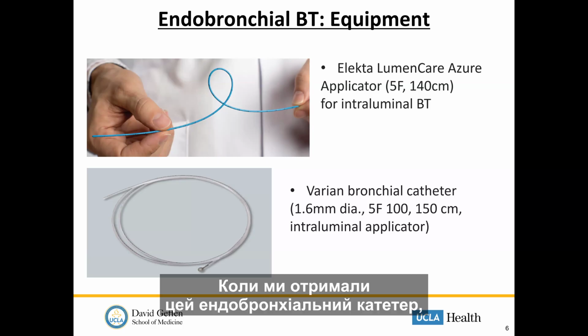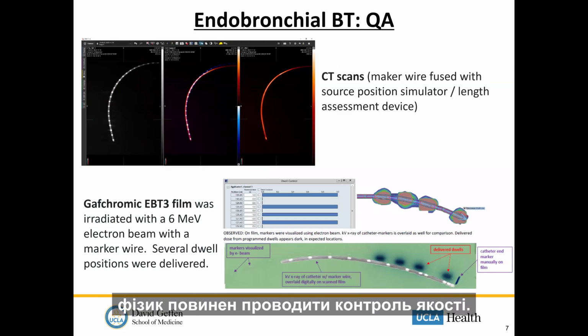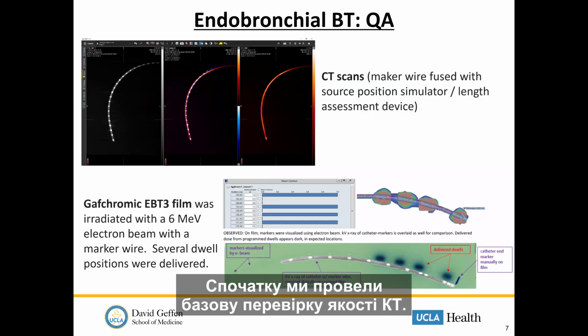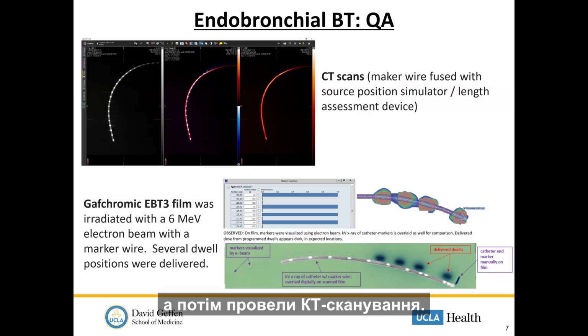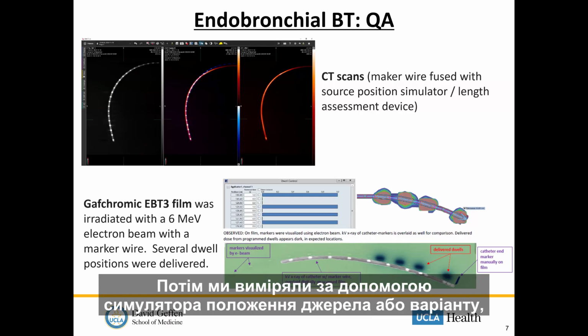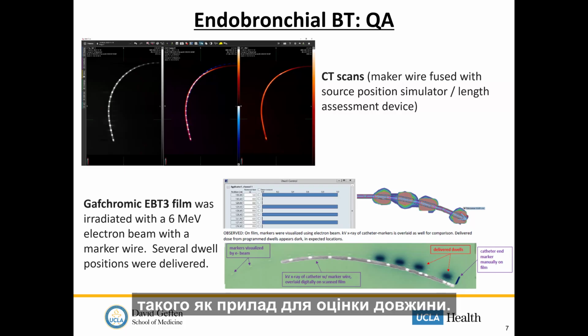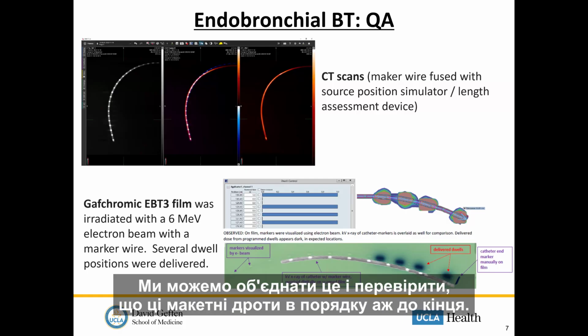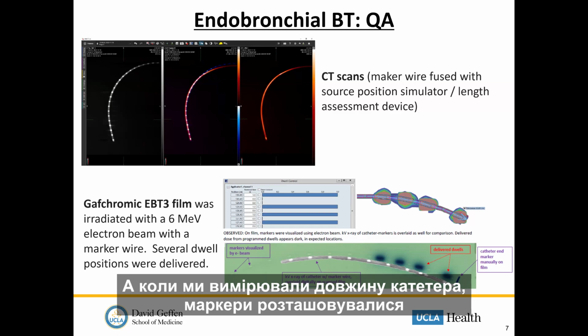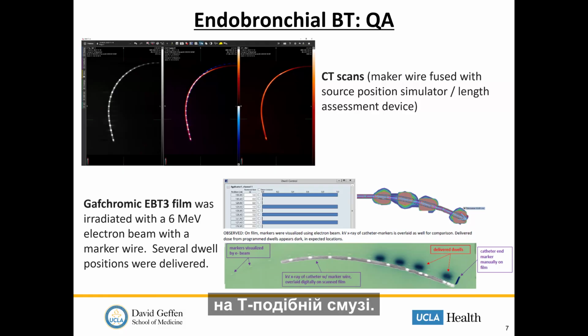When we receive this endobronchial catheter, the physicist must do the QA. First, we perform the CT-based QA. We put the dummy wire in the catheter, do the CT scan, and then measure with the source position simulator or the Varian-type length assessment device. You can see the marker at the tip end. We can fuse that and verify these dummy wires are located all the way to the tip end, and when we measure catheter length, the markers are located at the tip end.